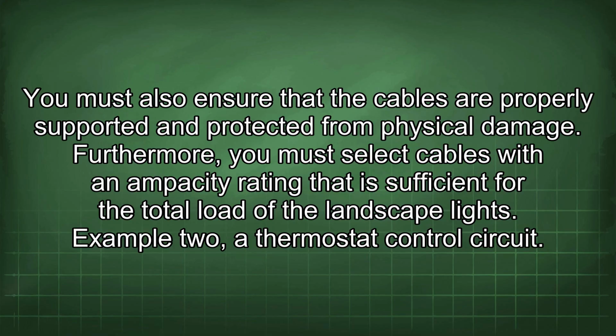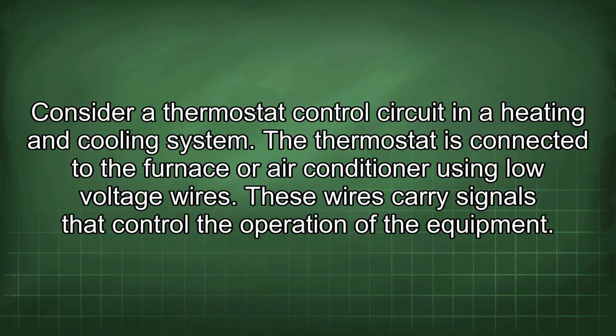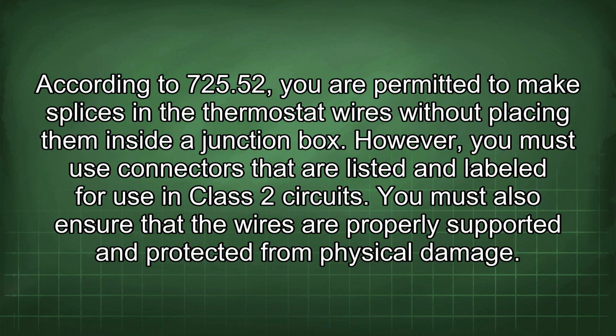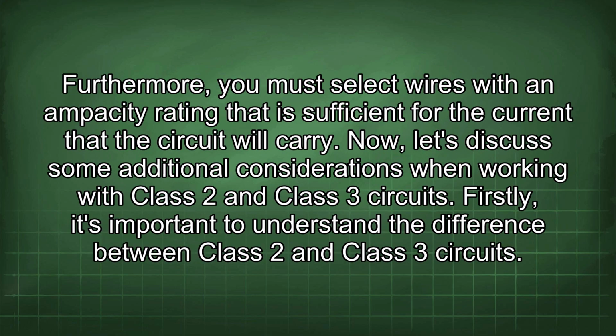Example 2: A thermostat control circuit. Consider a thermostat control circuit in a heating and cooling system. The thermostat is connected to the furnace or air conditioner using low-voltage wires. These wires carry signals that control the operation of the equipment. According to 725.52, you are permitted to make splices in the thermostat wires without placing them inside a junction box. However, you must use connectors that are listed and labeled for use in Class 2 circuits. You must also ensure that the wires are properly supported and protected from physical damage. Furthermore, you must select wires with an ampacity rating that is sufficient for the current that the circuit will carry.